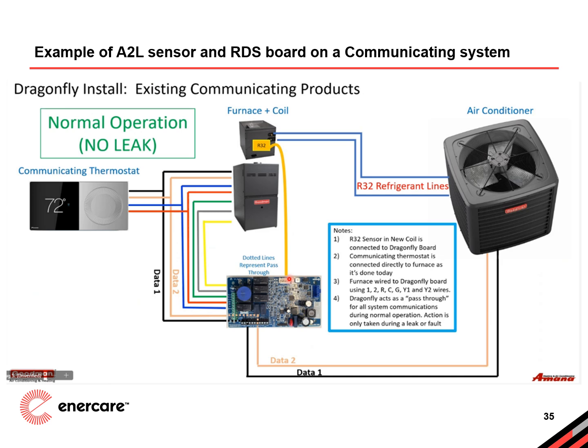Here we're looking at how the RDS board integrates into a communicating system with a Daikin. Let's break it down. The RDS sensor is mounted to the coil and it communicates with the Dragonfly board. In this setup, the Dragonfly board still acts as a pass-through for all the thermostat and furnace communication signals during normal operation. Like right now, where we can see everything running smoothly with no leak detected. The system continues to operate as intended, and any data passes through it seamlessly.